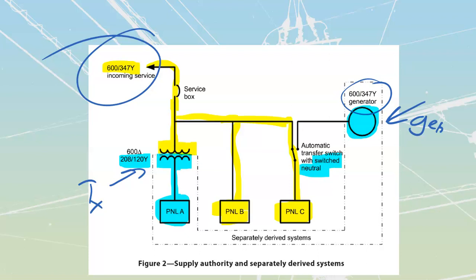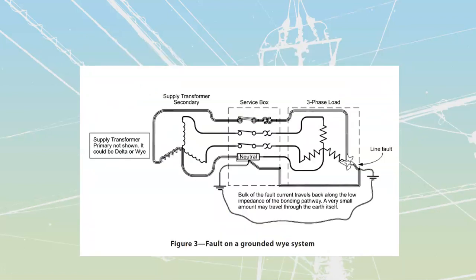Okay, let's take a look at what actually happens when we go underneath a fault. Over here, we're looking at that same grounded Y system, and we are going to take a look at our fault current. The first thing we're going to identify is the fault. So our fault point happens right over here, where I make connection from one of my lines over to one of my bonded metallic pieces. And this is the most common thing that's going to happen. It's very rare that you drop a live line directly onto earth, like dirt itself, but it's very common that we bring it into contact with something that is bonded.